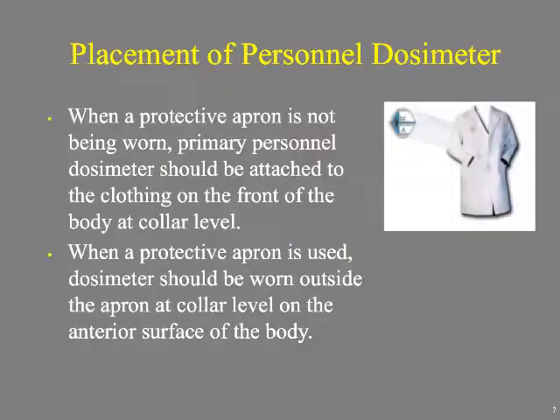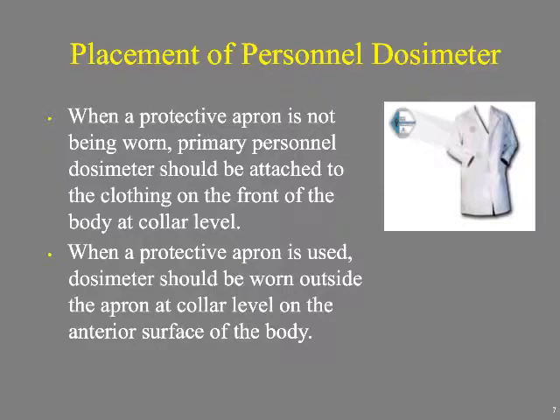We know these need to be worn at collar level. It's recording what we call an eye dose, and the only way to do that accurately is to have it close to the eyes. The thyroid is also very radiosensitive, so proximity to that organ matters. If wearing a lead apron, technologists need to wear the dosimeter on the outside of the apron.